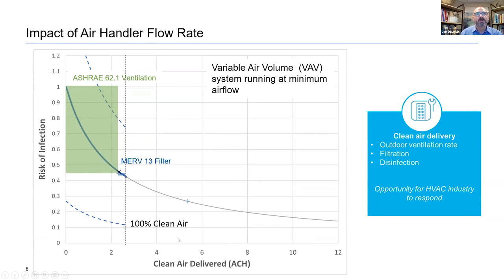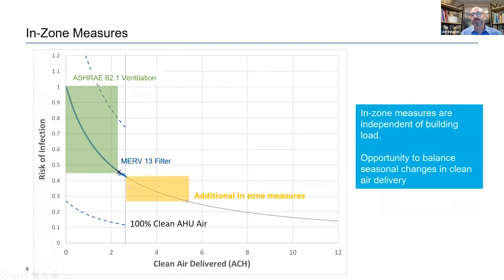So what can we do about it? What we can do is add another source of clean air, and that is in-zone filtration. This box shows the benefit of a 600 CFM fan filter unit, which gives you about 2.5 air changes per hour. This in-zone filter makes up for the difference of the reduced airflow rate from the centralized HVAC system and gets our infection risk back down to the same levels we had with the full airflow of the full design HVAC system.